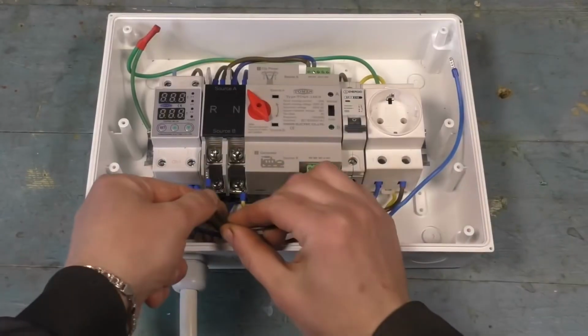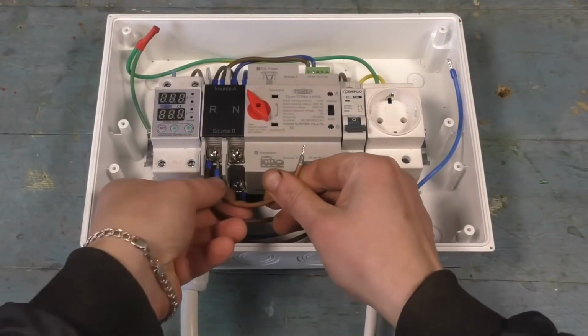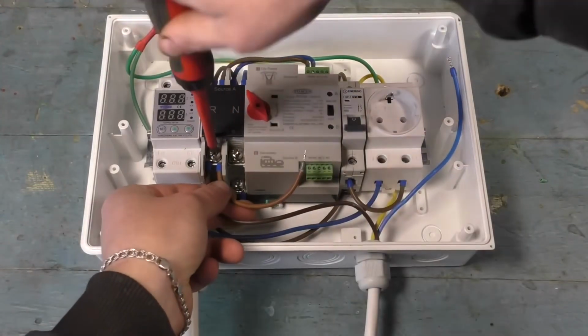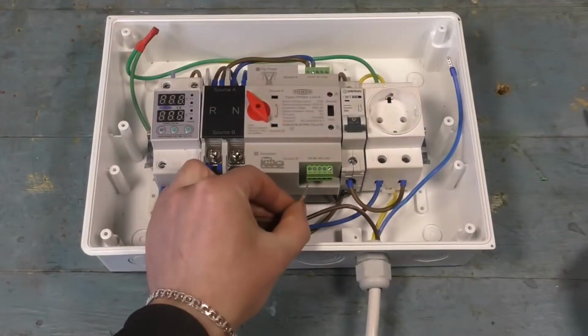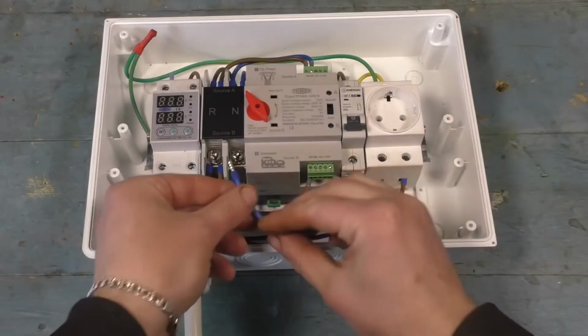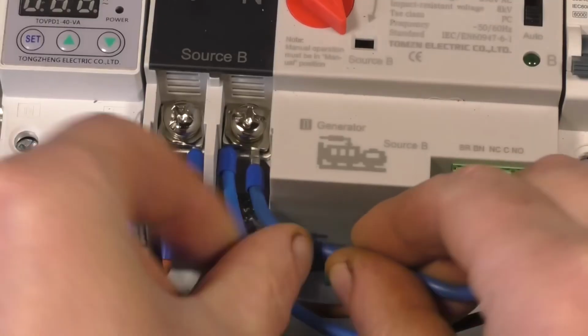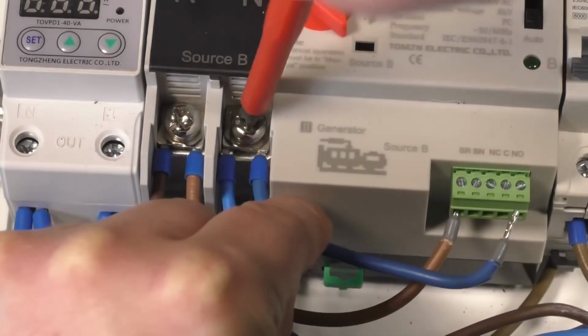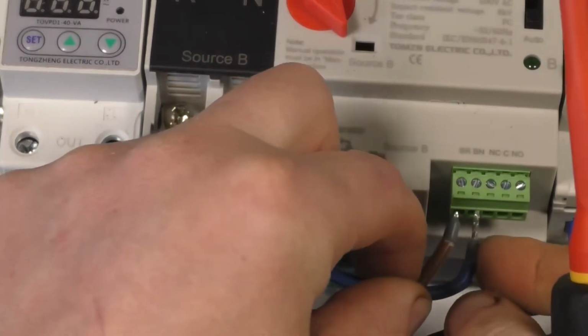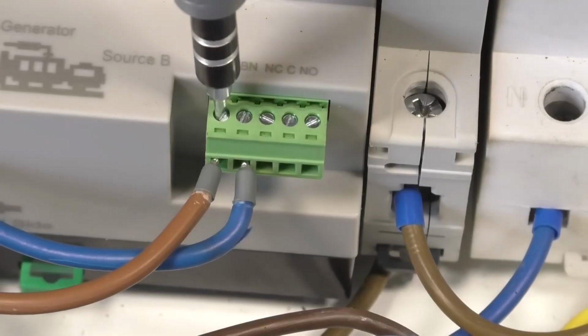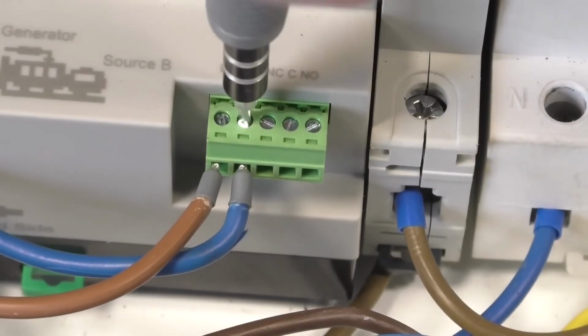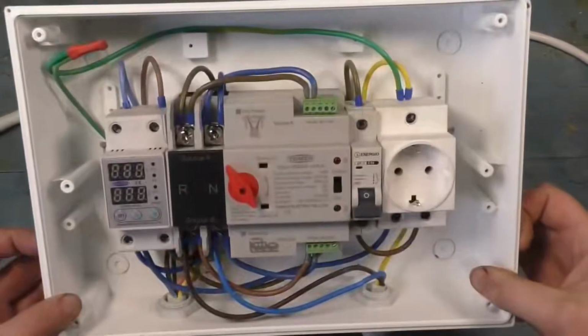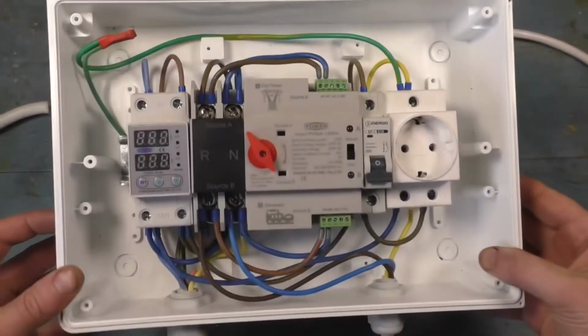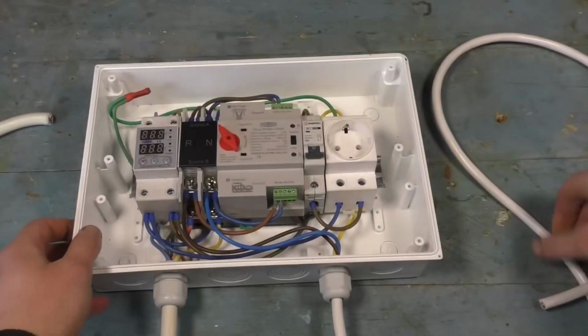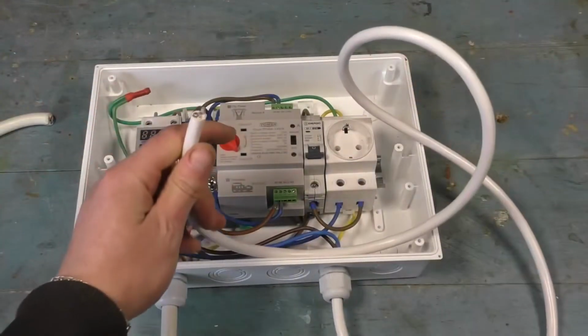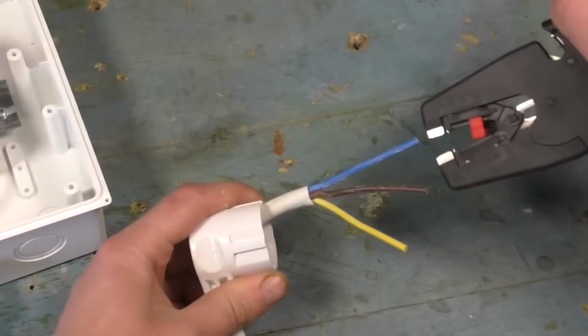The remaining 2 wires need to be connected to the output. In the ATS from Thomson, I immediately add the jumpers that need to be connected to the green terminal block to the BR and BN contacts. At this stage, the connection of all the modules in the panel is complete. As you can see, everything is done reliably and it is safe to connect a charging station to such a panel. Next, you need to connect a plug to the 3-core cable.